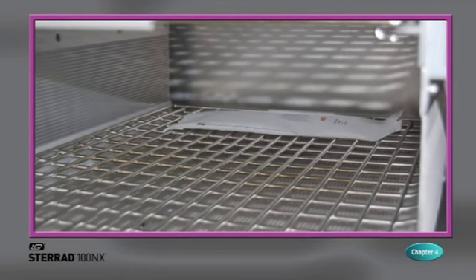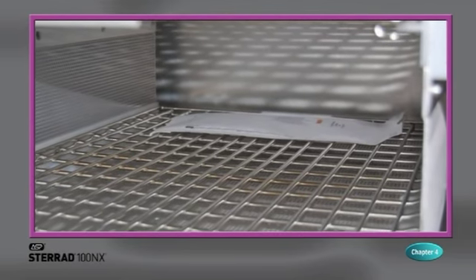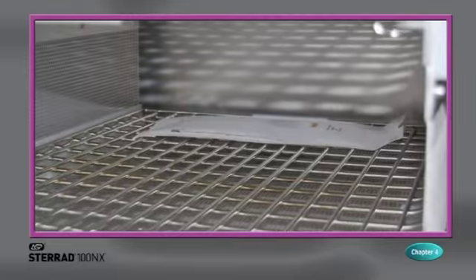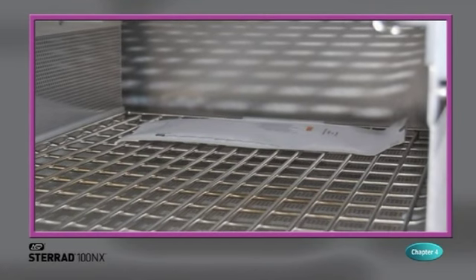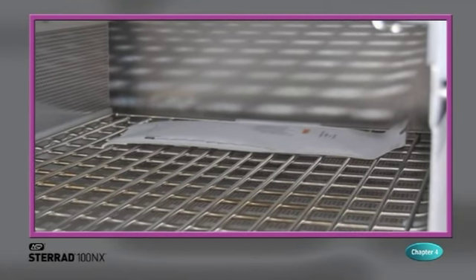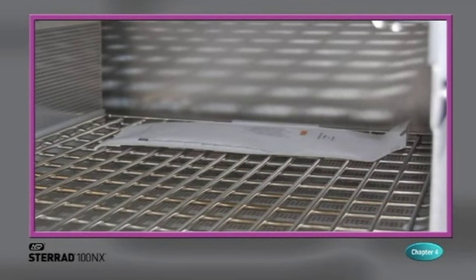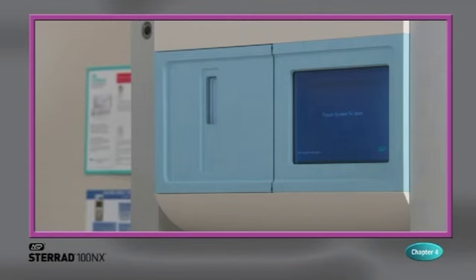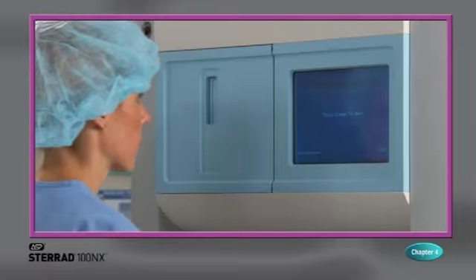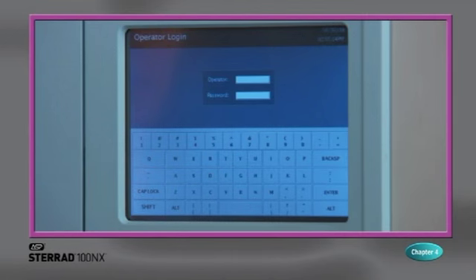Biological testing should be performed at least once per day for each type of cycle, or as specified by your facility's policy and procedures. For complete instructions, please refer to the Sterrad CycleSure 24 BI instructions for use. When you touch the Touch Screen to Start screen, the sterilizer displays the operator login screen.